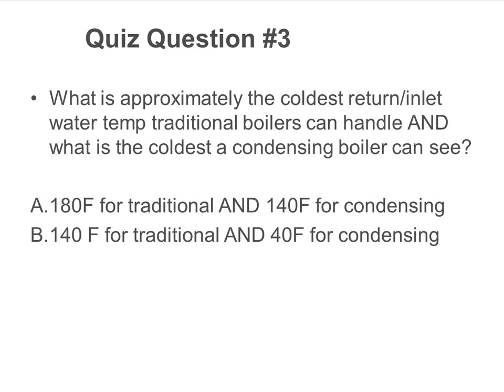So only a little more than half of you actually got the correct answer. The correct answer is about 140 degrees for traditional boilers. You can kind of push your luck with 130 maybe. Just kind of depends. You'll be on the fringe of condensing there. But for condensing boilers, a lot of you guys chose 90 as the minimum, which it can definitely be way colder than that, right? We can take it down to 32.1 degrees, basically. If it's not frozen, we can pump it.